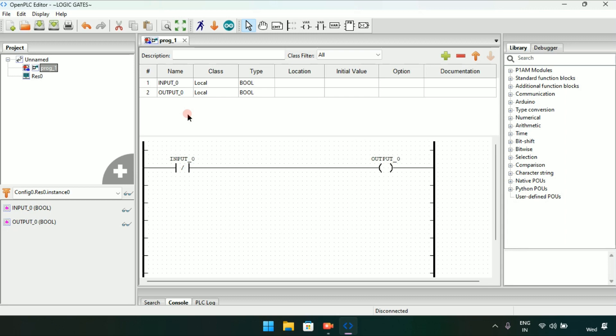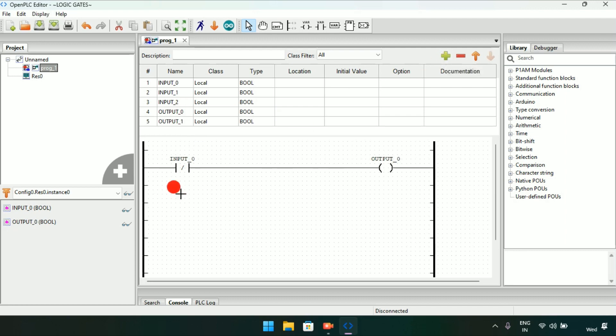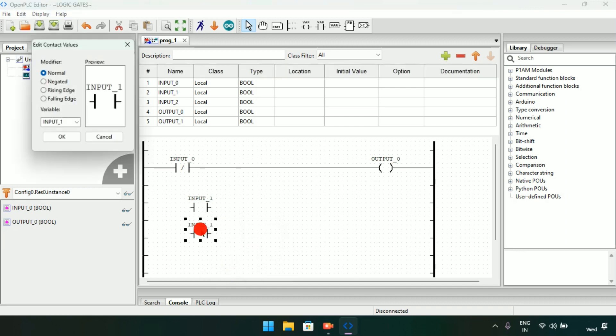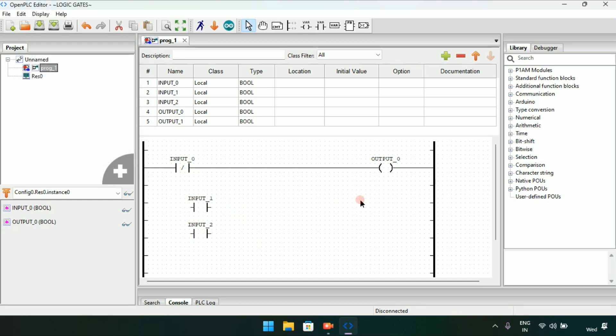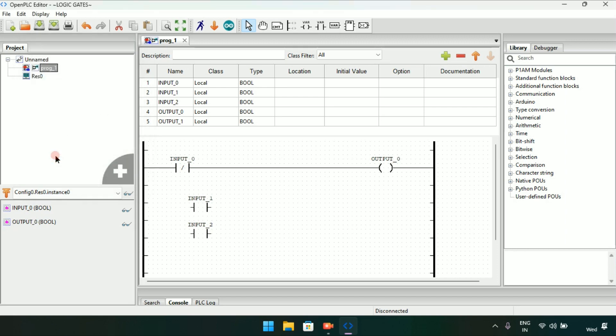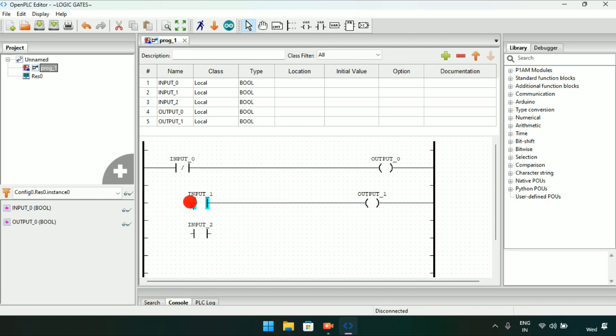Now let's start making the ladder diagram of the OR gate. First I will create some variables and an output. I will add a contact for input, adjust its size, copy it and paste a second input, then double-click and rename it 'input second'. I will add a coil for 'output first', adjust its size, connect the pins, and put input second in parallel.